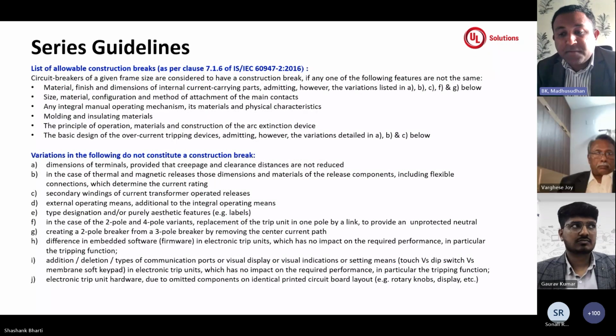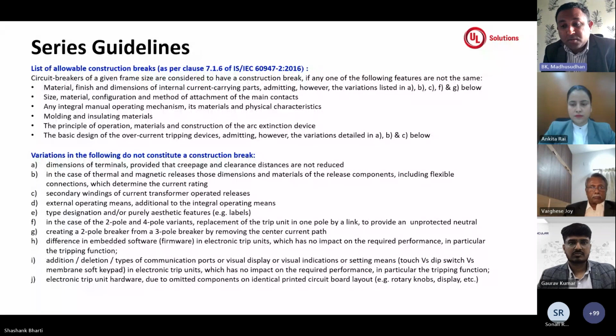Yeah, as I was specifically stressing the frame sizes and the various guidelines that are coming up. So if a customer wants to declare a specific construction break within that frame size, there are guidelines from the standard and also from the QCO. For example, if your product has similar material, finish, and dimension of the internal current carrying parts, excluding the variations allowed below, based on the dimensions of the terminals. In case of thermal and magnetic, the design should be the same. You can have an increase or decrease in the width or the thickness of the material that is allowed, and also the secondary winding of the transformers. Plus other cases, like if you are doing a single pole with a similar construction and you are multiplying it to a double pole, 3-pole, or 4-pole. So these are the variations allowed.